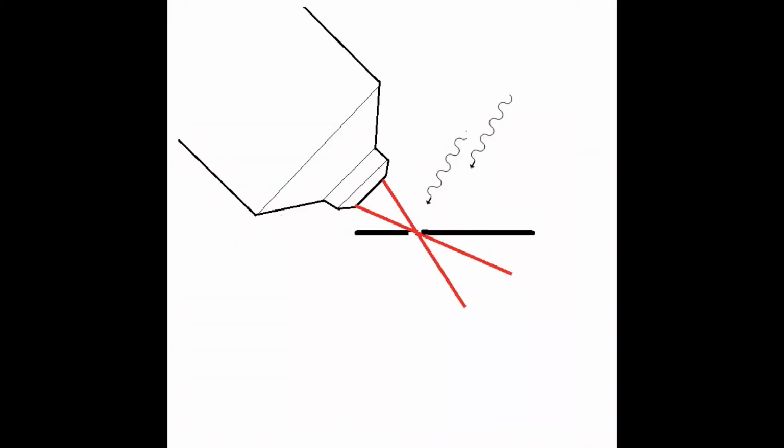You're going to start the alignment acquisition and move the specimen stage to the end of the slotted silver specimen that has the 1,000 micron or 1 millimeter slot. As you move into the slot, the counts will drop off. As you move out of the slot, the counts will come up. By correlating the counts to the position of the specimen stage, you can determine where the analyzer is looking inside of the slot. Position the silver specimen to the end of the 1,000 micron slot and put a mark on the TV monitor. This is your initial alignment spot.